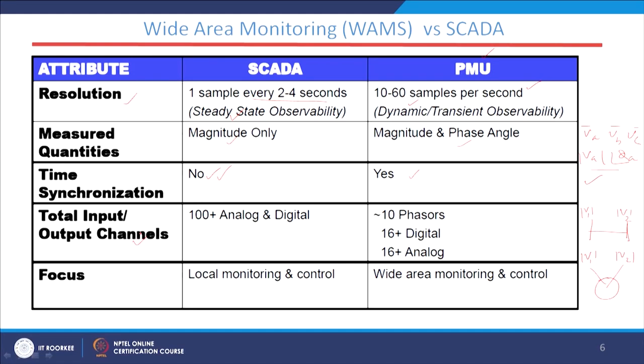The GPS system provides a common reference clock or universal clock signal to each PMU station where PMUs are installed. As far as total input/output channels are concerned, SCADA has 100-plus analog and digital channels, while PMU has 10 phasors — which include both magnitude and phase angle — along with 16-plus digital channels and 16 analog channels. The focus of SCADA is local monitoring and control, whereas WAMS provides wide area monitoring and control over a very large network.